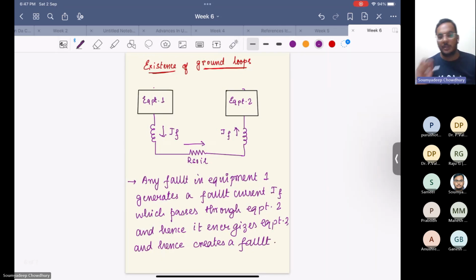So this thing is clear. These ground loops, any confusions? Any doubts? Why we should avoid ground loops? Is it clear? Yes, this is the reason why we are putting gravel in a substation, where the transformer equipment, the switchgear and everything are there. Yes, you're correct. This is the main reason we put gravel, to provide a high resistance path, because while grounding, these equipments will be anyhow connected. You cannot avoid the connection between the equipments through the soil, but you can break these ground loops by placing some high resistivity materials like gravel or soil, something like that. Yes, you're correct.